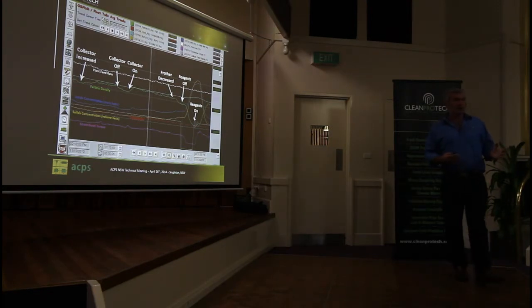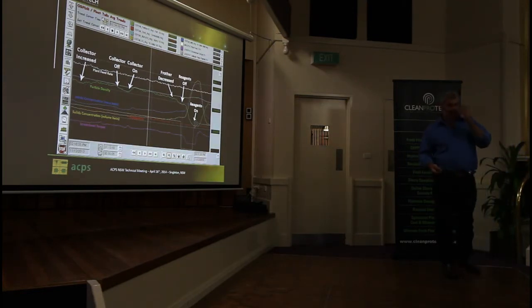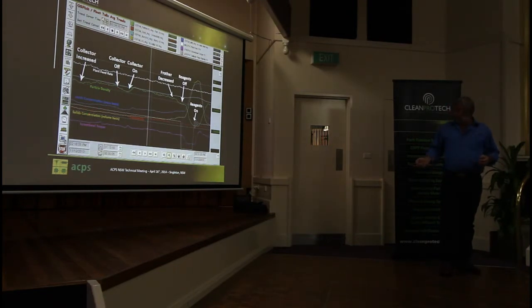I suppose the real power of the unit comes in when it detects things that you don't expect. Like the other day, I believe it was very interesting. I wasn't there, but Nicholas and Rod were. The plant's going along, screen bolt torque sitting nice and level, but what happened was that the particle density went down in the tailings and the solids concentration came up.